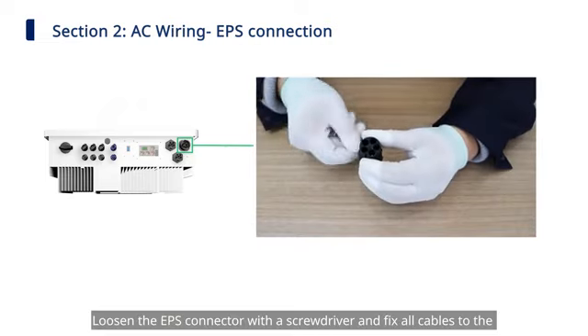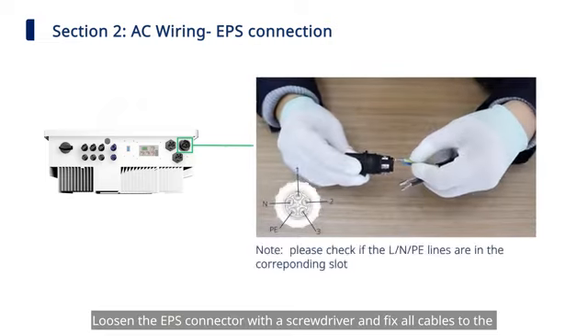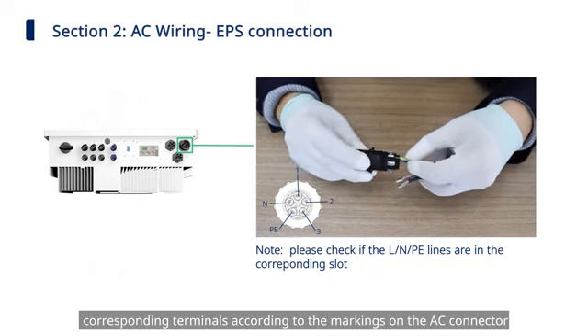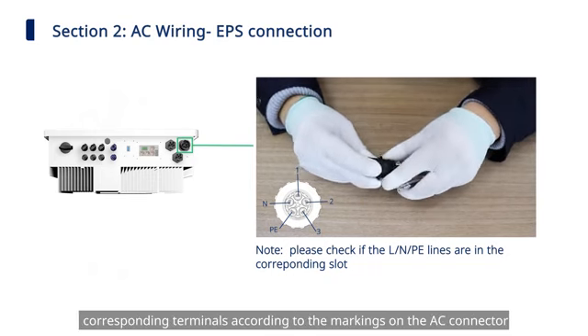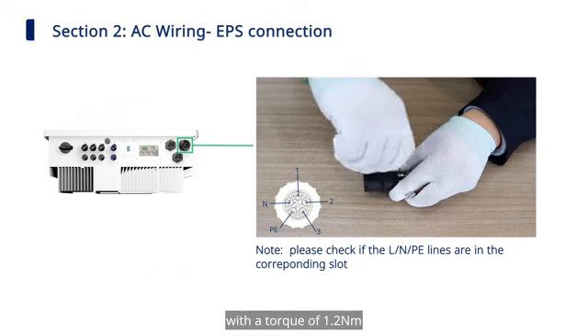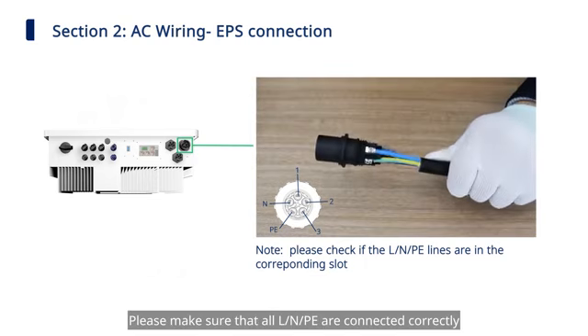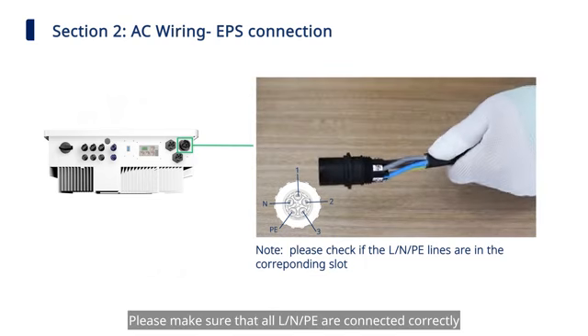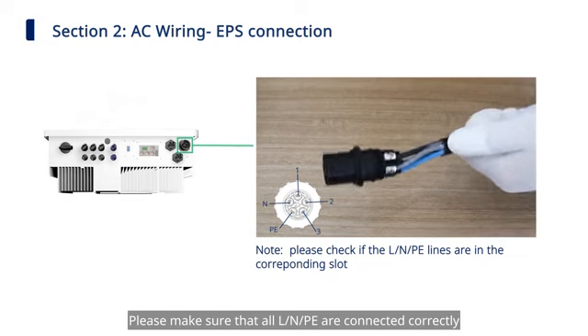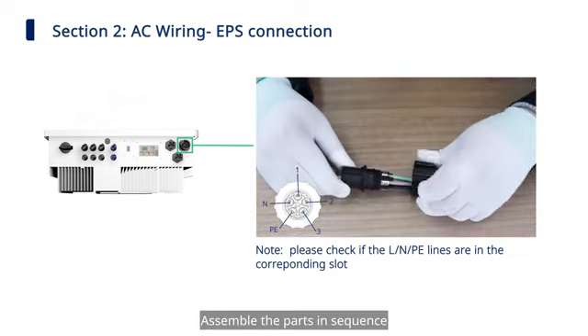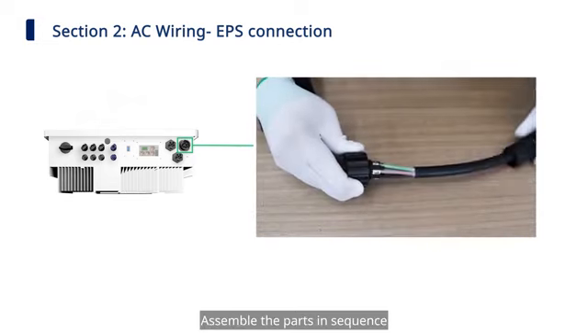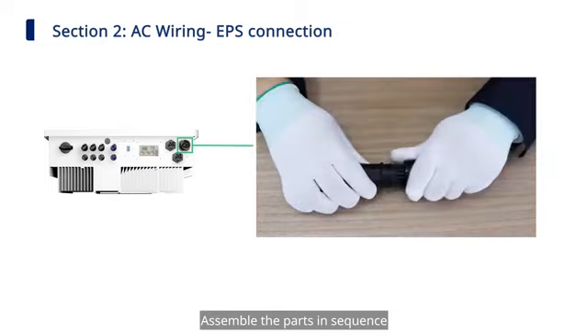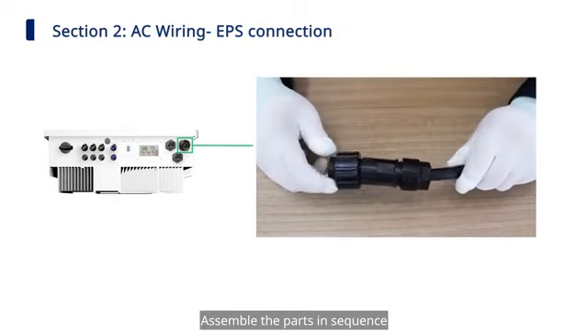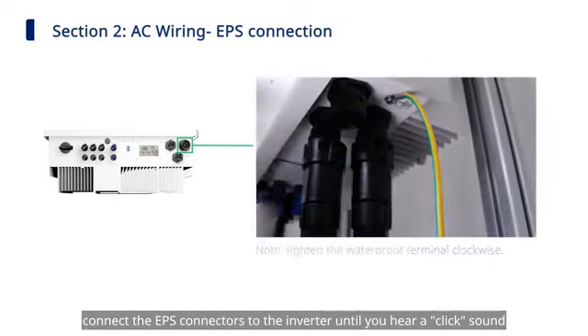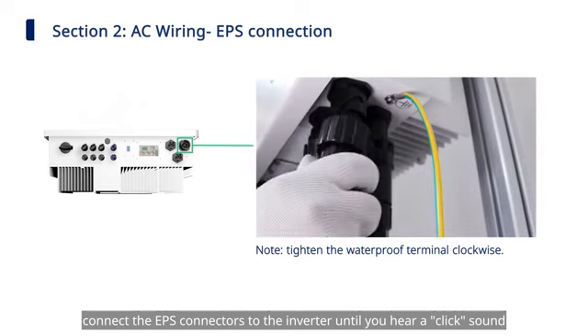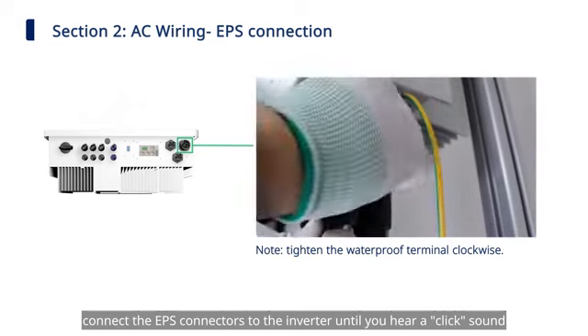Loosen the EPS connector with a screwdriver and fix all cables to the corresponding terminals according to the markings on the AC connector with a torque of 1.2 Newton-meters. Make sure that all L, N and PE lines are connected correctly. Assemble the parts in sequence. Finally, connect the EPS connectors to the inverter until you hear a click sound.